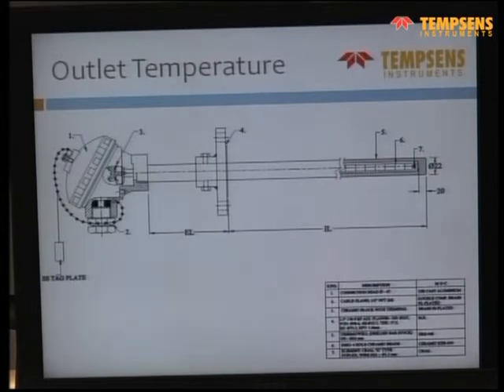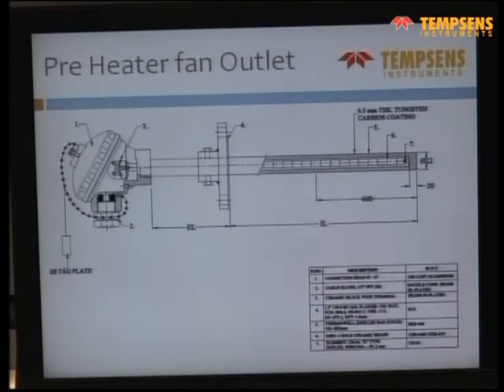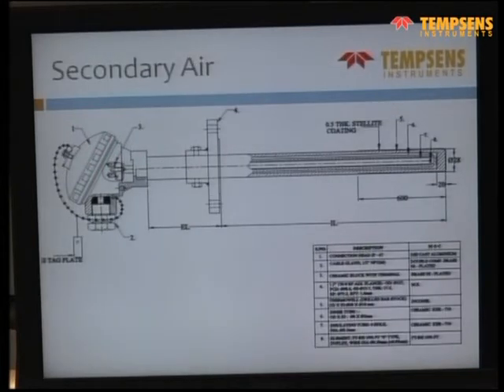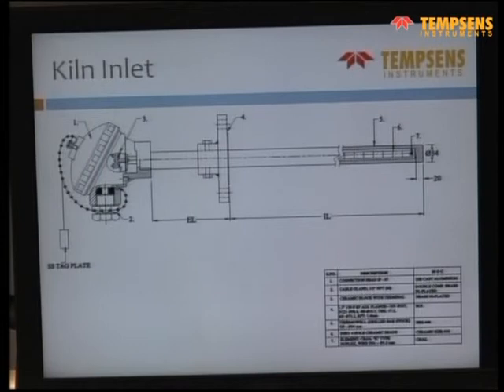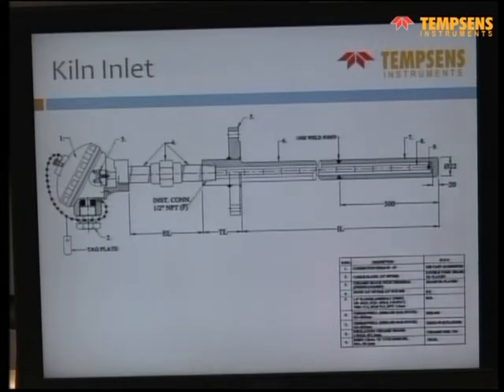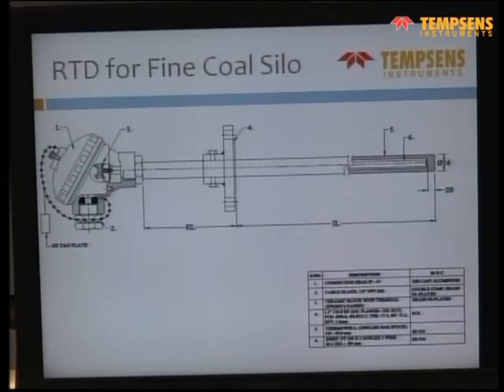Aggressive in terms of abrasive, because the clinker is touching and it is of high temperature and very abrasive nature, so it eats away the outer protection tube. This is again mainly HRS, also can be coated with tungsten carbide. In this case it is for preheater fan outlet. For secondary air also a similar HRS thermowell, and with some coating can be there. For the inlet also similar thermocouples are there. This is another design with a different kind of process connection, which is flanged. This is for coal silo. Here the temperature is not much, so here it can be SS316 or can be tungsten carbide also.